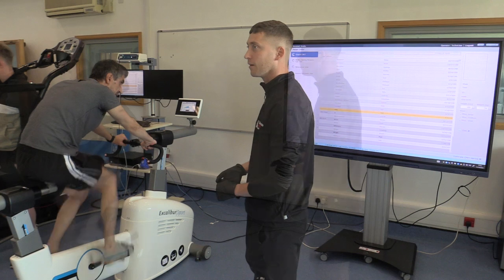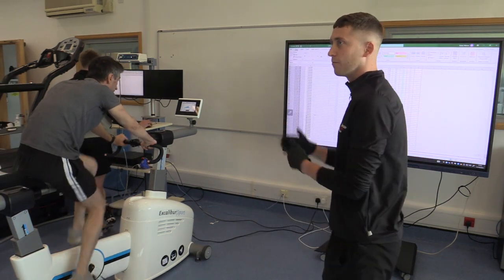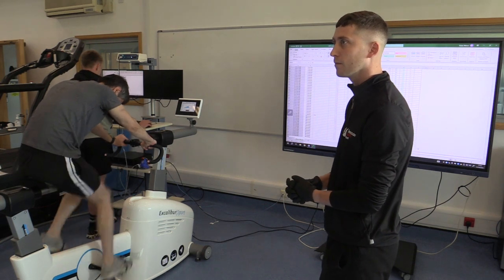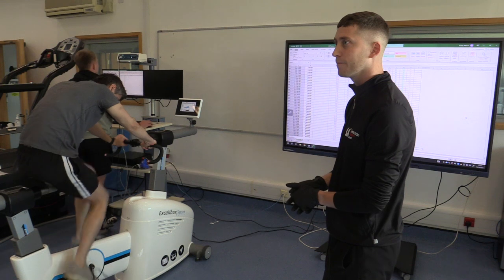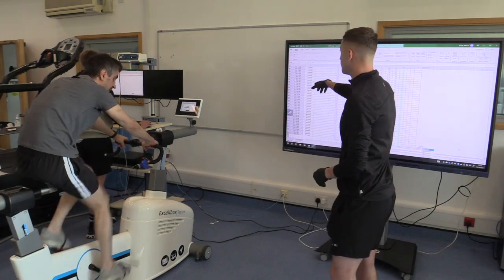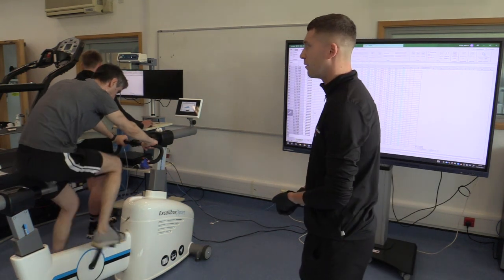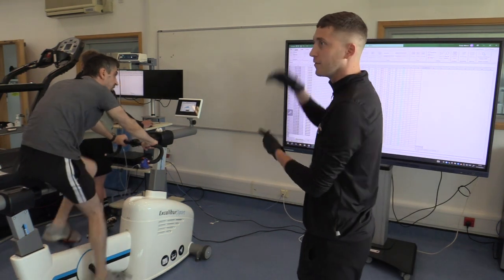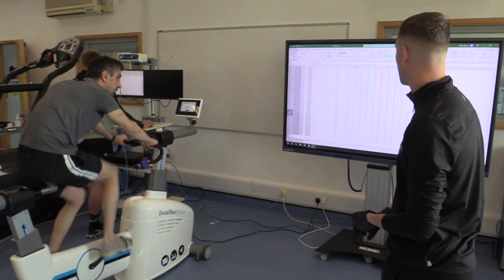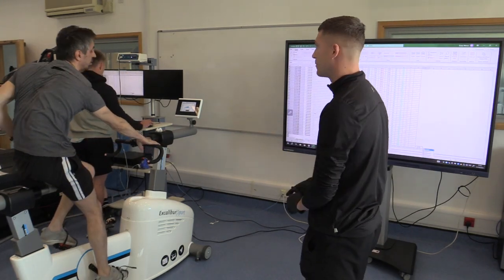Was there a set protocol for VO2 max from that? Was it a rolling 15 second average, 30 second average, anything like that? The protocol says between 8 and 15 seconds. Ours is set to give a second by second average as we go through. Generally, if I'm doing it, I use a rolling 15 second average and take the highest, excluding some sort of outlier in there. I feel most comfortable saying that as soon as we have 2 rounds.